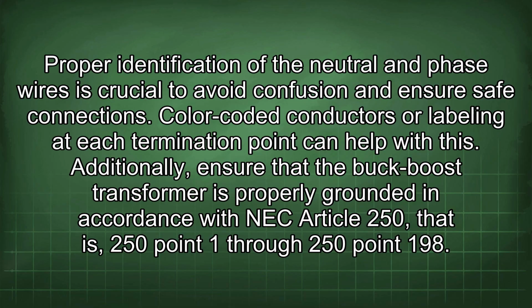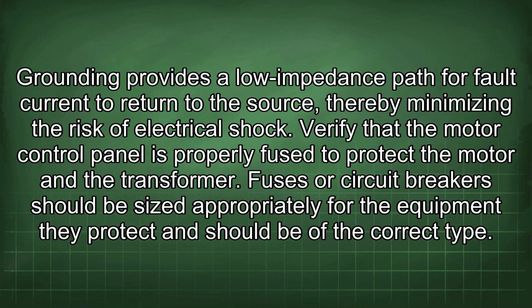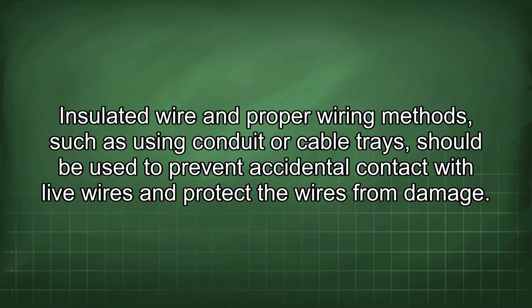Additionally, ensure that the buck-boost transformer is properly grounded in accordance with NEC Article 250, that is 250.1 through 250.198. Grounding provides a low impedance path for fault current to return to the source, thereby minimizing the risk of electrical shock. Verify that the motor control panel is properly fused to protect the motor and the transformer. Fuses or circuit breakers should be sized appropriately for the equipment they protect and should be of the correct type. Insulated wire and proper wiring methods, such as using conduit or cable trays, should be used to prevent accidental contact with live wires and protect the wires from damage.